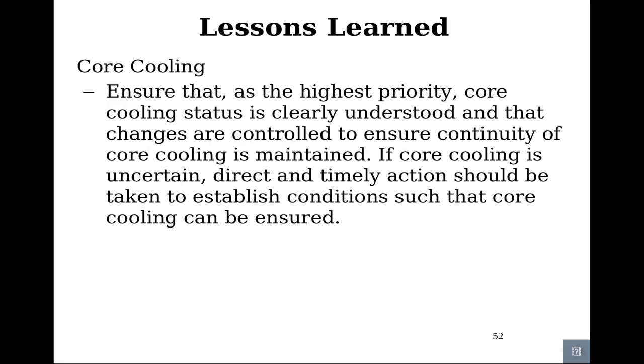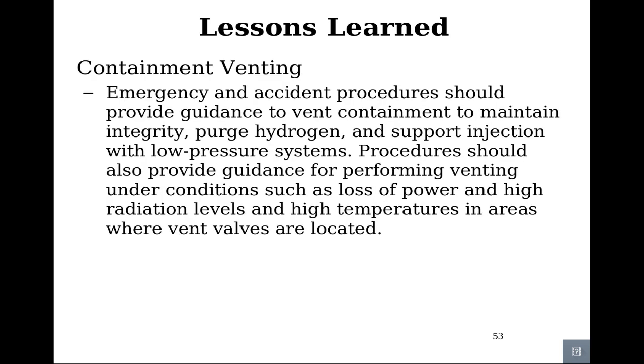Core cooling. Ensure that, as the highest priority, core cooling status is clearly understood and that changes are controlled to ensure continuity of the core cooling is maintained. If core cooling is uncertain, direct and timely action should be taken to establish conditions such that the core cooling can be ensured. Containment venting. Emergency and accident procedures should provide guidance to vent containment to maintain integrity, purge hydrogen, and support injection with low pressure systems. Procedures should also provide guidance for performing venting under conditions such as loss of power, high radiation levels, and high temperatures in areas where vent valves are located.